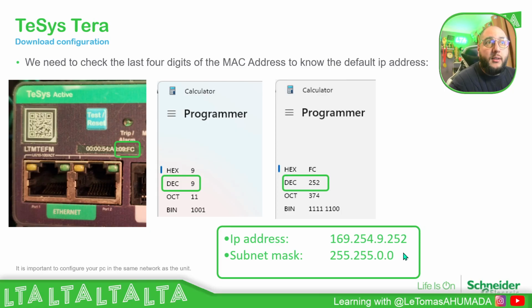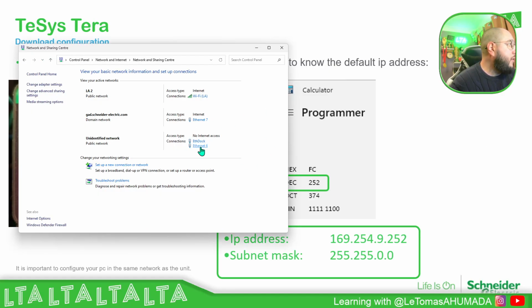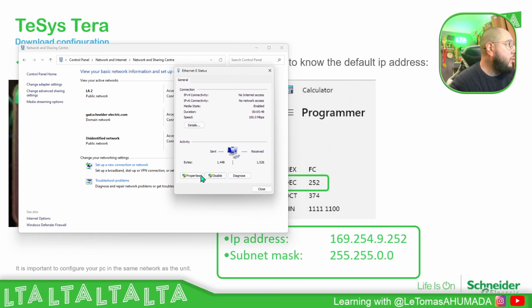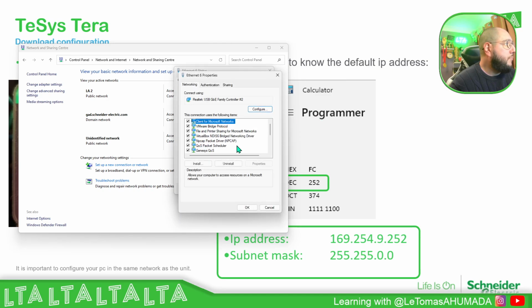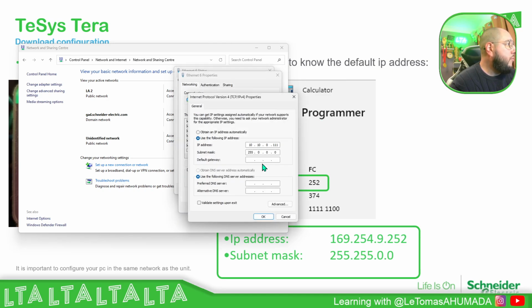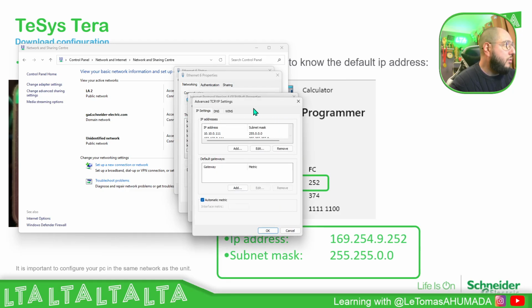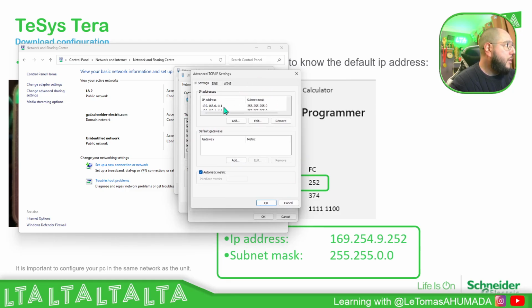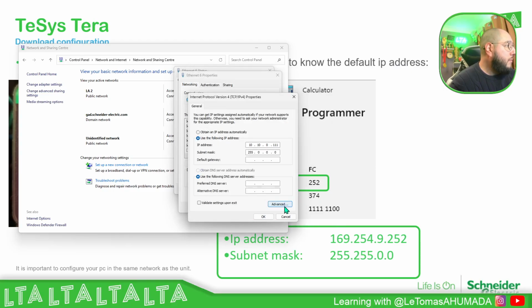Now, in order to connect, this is not enough. What we need to do is open our control panel, go to the Ethernet port that we're going to use, properties, find TCP/IP version 4, and here you can type something in the same network, or go to advanced in case you're going to connect to multiple things and add the one you're going to connect to. In my case, I have 169.254.0.101 and the subnet mask 255.255.0.0. You can see here it is in the same network.